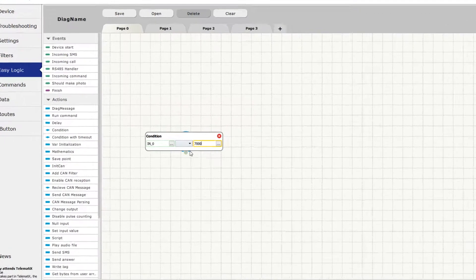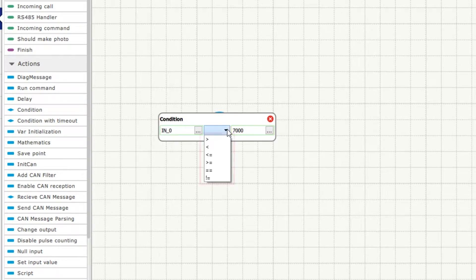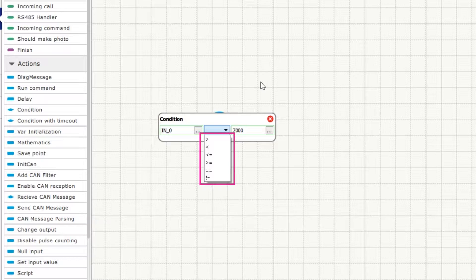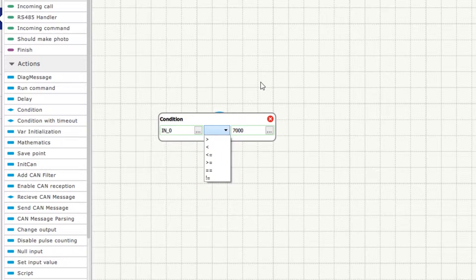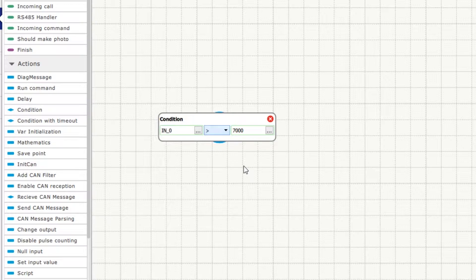Condition can use one of six different arithmetical signs to compare left and right sides. It can be less, more, less or equal, more or equal, equal and not equal. We decided that ignition is ON when voltage is above 7V. So we use the MORE sign.